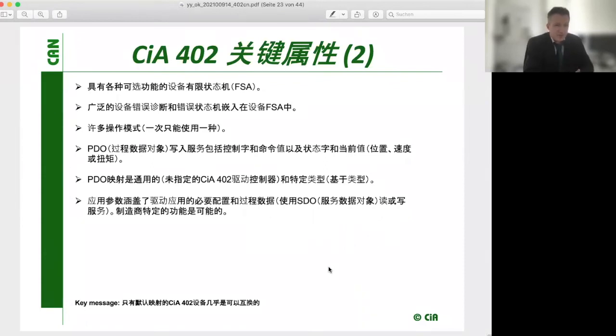There are multiple application modes, operation modes, in there. So you can synchronously drive by position to a defined position. You can drive and control the current consumption with what is called torque mode. You can have closed loop control. You can move in a very slow motion, accelerating until the maximum speed, and then decelerating to a very slow motion. Based on the other profile, there will be the velocity profile. Such things are an integral part of the specification. It's very helpful, and you decide which modes you implement in your drive.